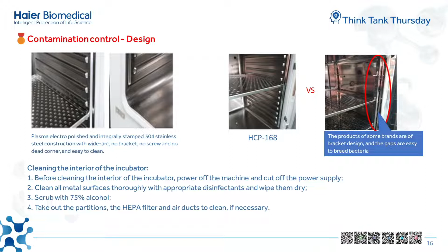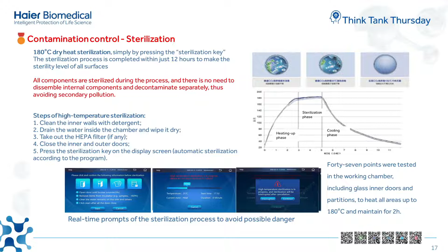Although we understand that different kinds of laboratories' standardization can vary, we understand that the 304 stainless steel internal chamber can be widely applied across those different standards. As mentioned before, we adopt the 180 Celsius degree dry sterilization methodology. All components are sterilized during the process, and there is no need to disassemble internal components and decontaminate separately, thus avoiding secondary pollution. And there's also a procedure listed for reference. And there are so many methods provided by manufacturers to facilitate incubator self-decontamination.